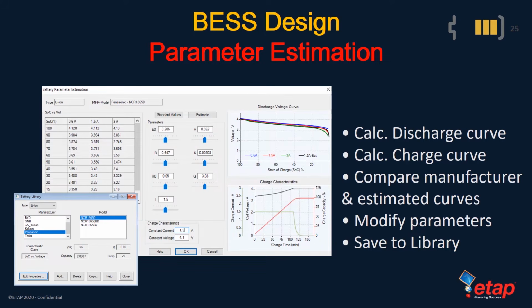Therefore, in ETAP, you can actually develop a battery inside the battery library and use battery parameter estimation to estimate the charge and discharge curves if they are not provided by the manufacturer. If they are provided by the manufacturer, you can also use parameter estimation to compare the manufacturer as well as the estimated curves. So let's take a look at the parameter estimation in action.